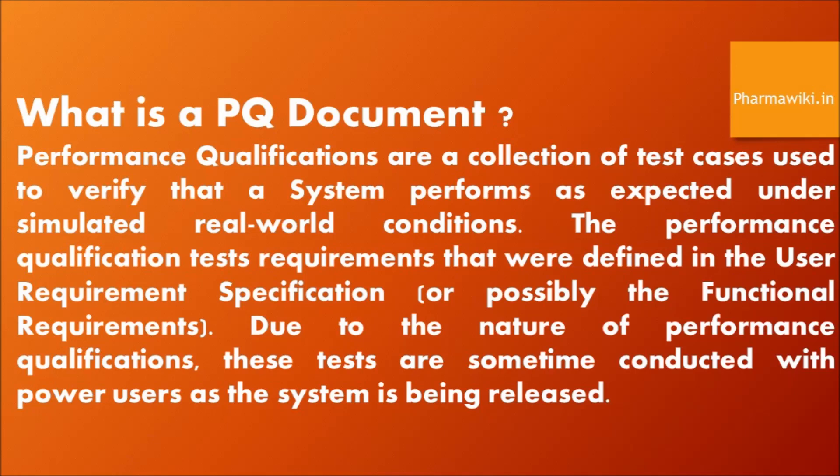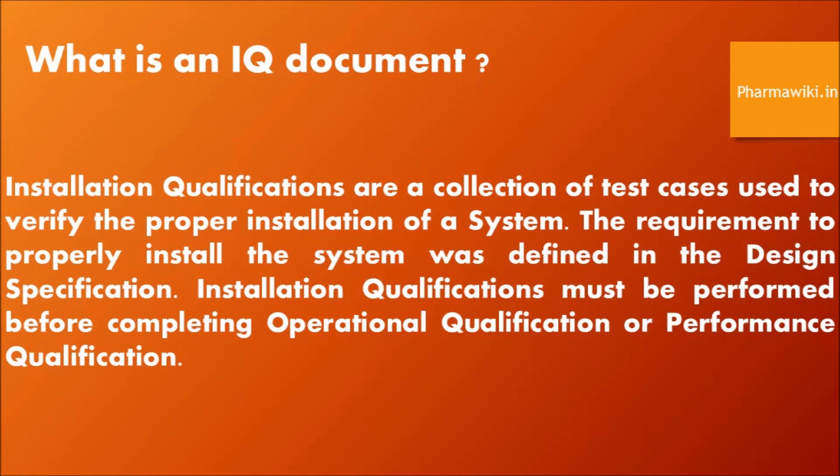Now, let us see what is an IQ document — that is, installation qualifications. Installation qualifications are a collection of test cases used to verify the proper installation of a system. The requirement to properly install the system was defined in the design specification. Installation qualifications must be performed before completing an operational qualification or performance qualification.